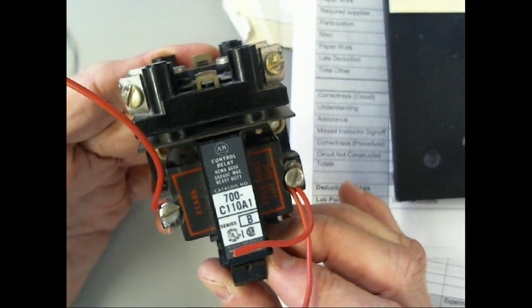You understand, of course they're encapsulated. They're usually - you can't repair the coil, but what you can do is you can replace the coil. Like I said on this one, we would break this screw right here loose, then we would take the spring off and this whole armature would pull out, and then the coil would slide out from the side. Then I could come in and replace the coil and just put it back together. So this guy here is very, very repairable. The contacts are easy to replace, they're just spring loaded in there if you had a bad contact. So these are very, very popular in industry because instead of buying the whole relay, you can just buy parts to keep them fixed.